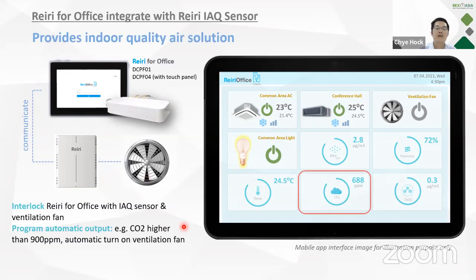For example, if the present level is 688 ppm, which is still below the preset limit of 900 ppm, it is still okay. But if it goes beyond 900 ppm, then ventilation is automatically turned on to bring fresh air from outside, reducing CO2 in the room. This is one example of smart control to improve the quality of life and indoor air quality for occupants.